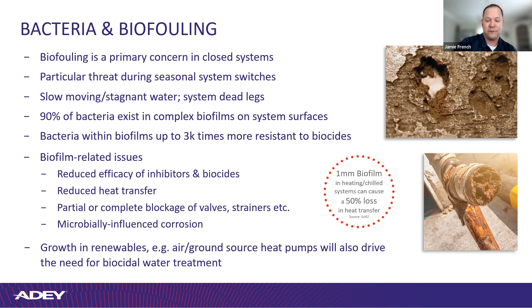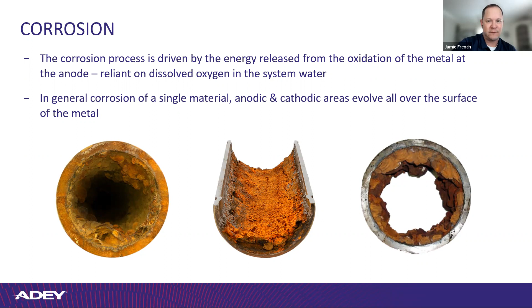And corrosion, that's the one we like to talk about. It's driven by the amount of oxygen that's in the system. Generally, when you have a single material, like they're showing steel pipe here, it looks like Sked 40, you get corrosion across the whole surface. So it's not just spotty. Once the corrosion starts, it's affecting the whole surface of the pipe work there.